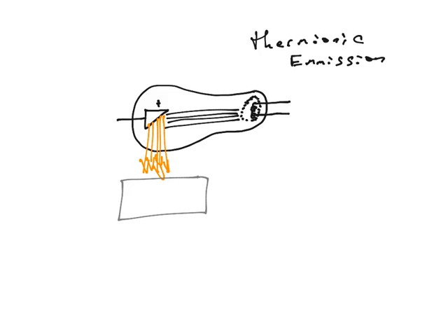So very, very good. However, this created a new problem. There were so many electrons being sent across at once, with such high energies, that it actually started to wear into the anode, the wedge-shaped anode here.